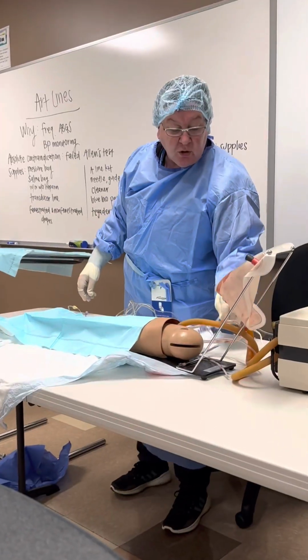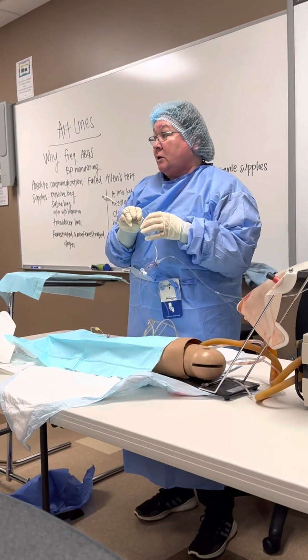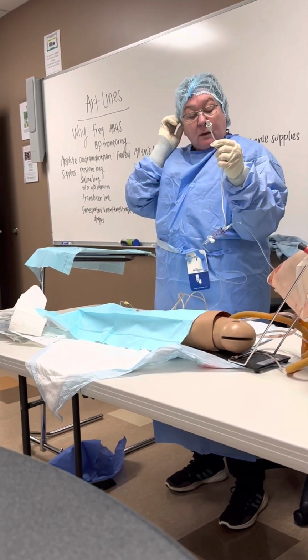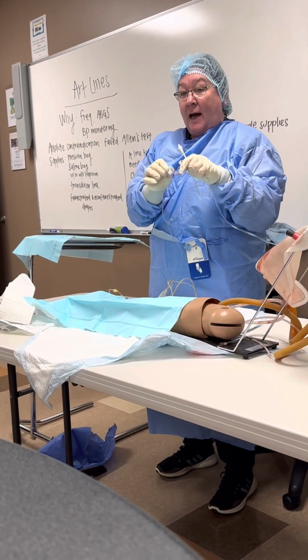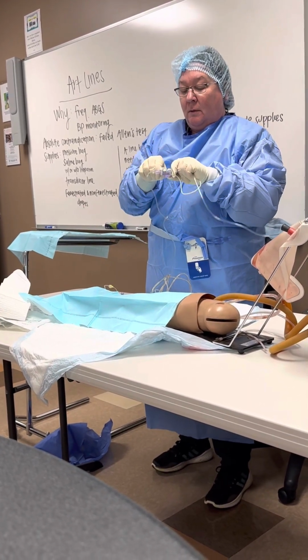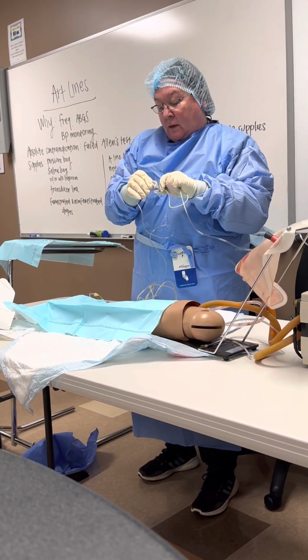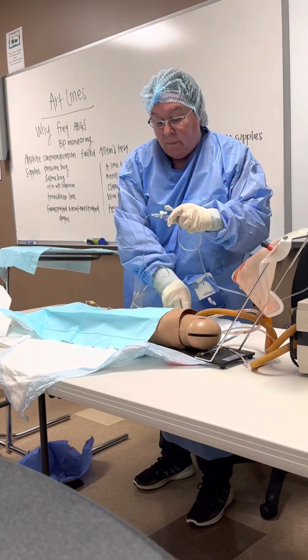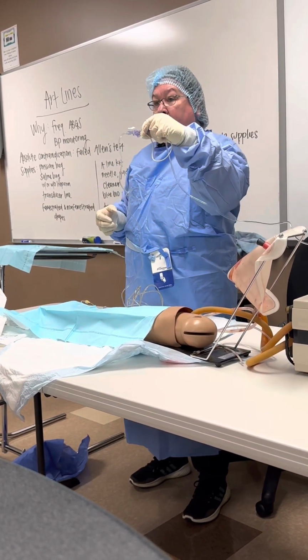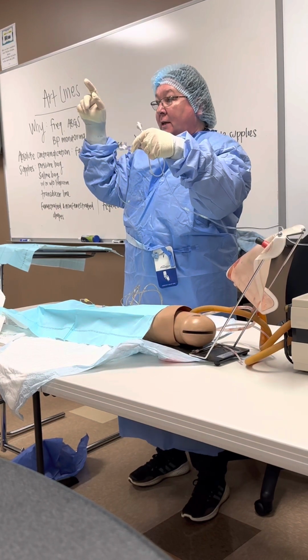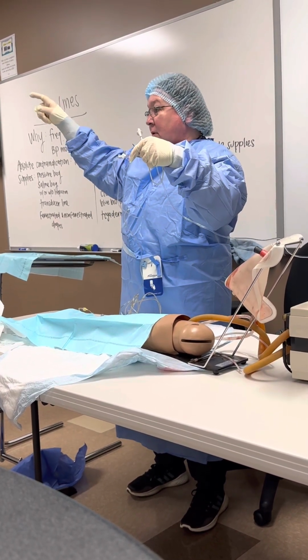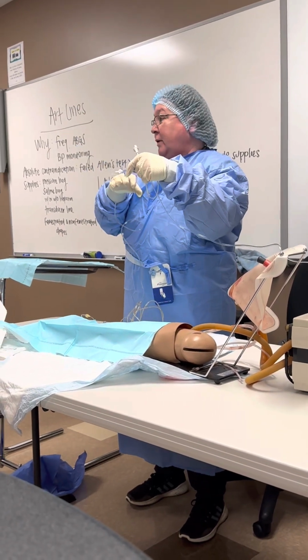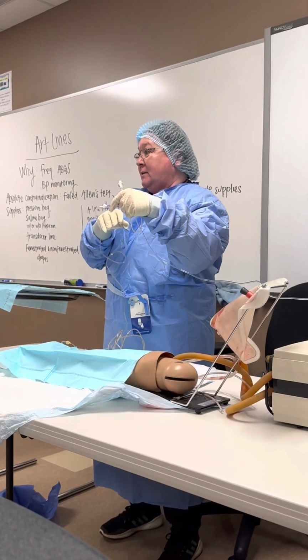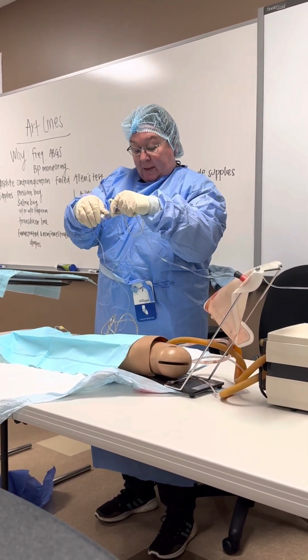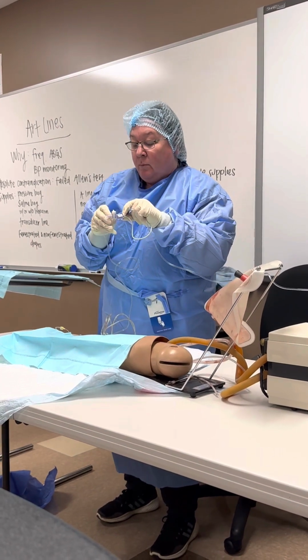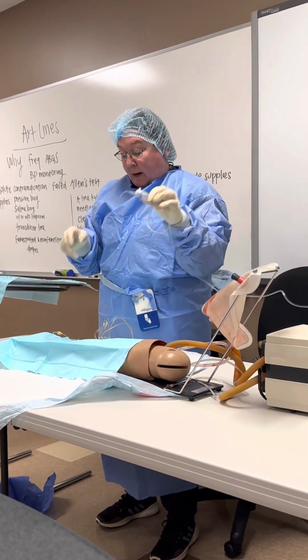When we zero the transducer, we're taking into account atmospheric pressure. So what you have to do is, when this is hooked up, you're gonna take the cap off here if it has the cap on. Just like that. Take the cap off and then turn it off to the patient. This is gonna account for the atmospheric pressure in the air. Hit 0 on the monitor, and now it's gonna zero it out, so it won't add that into the pressure for the patient. It's very important to get the proper pressure. So now we've zeroed it out. We can put this back like this, put the cap back on, and now you should get an accurate reading.